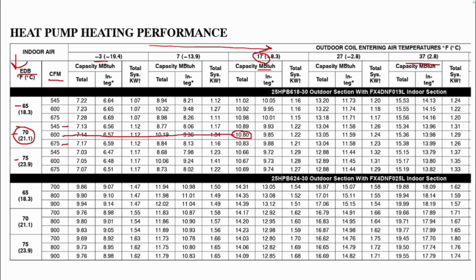10,800 BTUs when that system is running. Now, Carrier does this funny thing where they show you integrated capacity. What integrated capacity does is, over that hour of time, it takes into account the effects of defrost. When I go to defrost, I'm going to absorb heat from the inside and put it back outside to defrost the coil. And so that does have a little bit of an effect on the overall delivered capacity over that course of time.